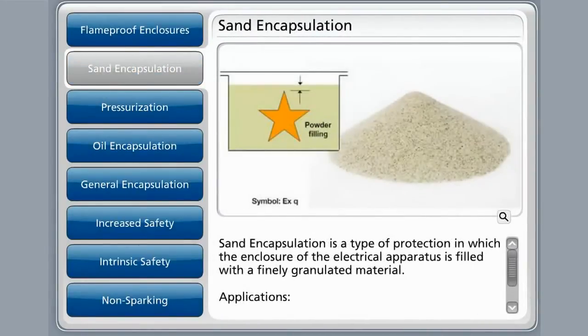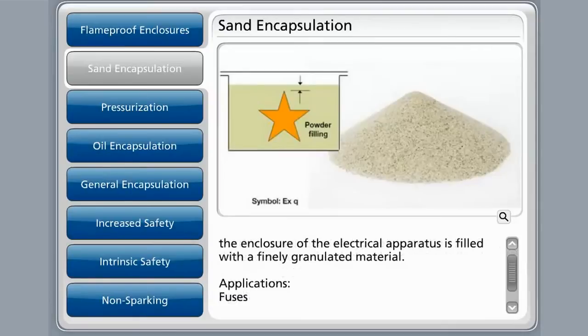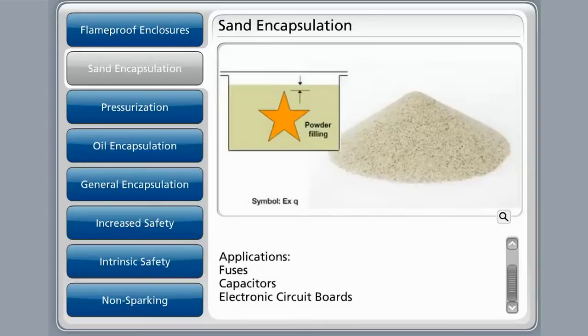Sand encapsulation is a type of protection in which the enclosure of the electrical apparatus is filled with a finely granulated material. This ensures that electrical arcs occurring within the apparatus will not ignite the surrounding atmosphere.